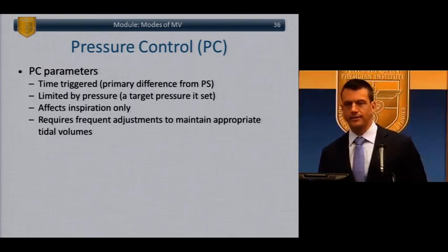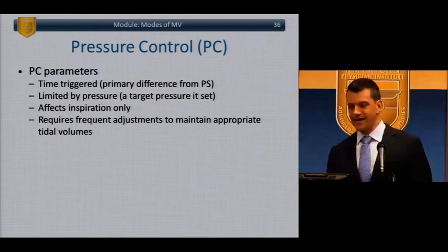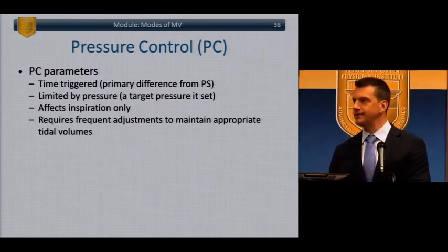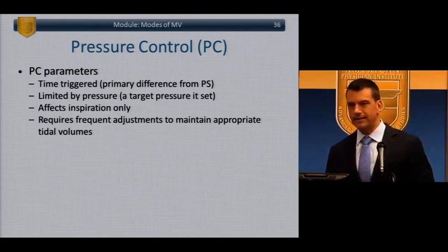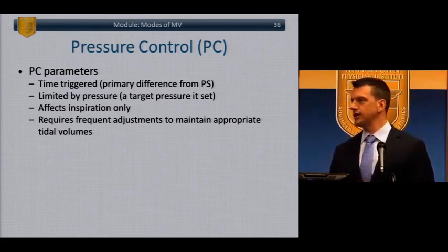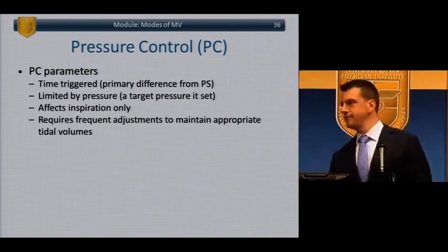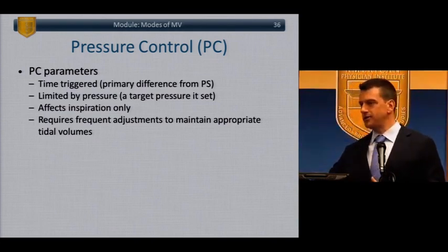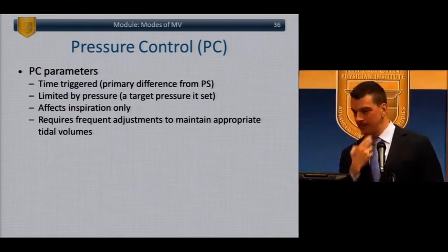Pressure control is kind of akin to, this was the earliest modes of ventilation, like driving a stick shift. Basically, you have pressure in the tube, and in the old ventilators, it was basically just a pressurized system, and you turned a valve on and off. Pressure went in, and you turned the pressure up, and the patient got a breath. You turned it down, and the breath was allowed to escape.